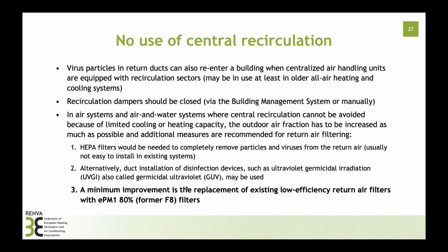But if it is a heating or cooling capacity issue, as it is in many cases, then it is recommended to increase the outdoor air rate to a minimum of 50% and then improve filtration of return air. So to be sure, one will need HEPA filters, but usually this is impossible because of the high pressure loss when installing such filters. Then other options are UVC, which can be used, or the minimum improvement that is recommended, which is with ePM1 80% filters.